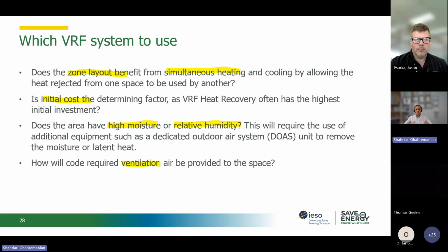Because with the VRF, we don't duct the air through the building, so we cannot add the fresh air to this heating and cooling system, basically. So we need to consider a dedicated outdoor air system, or DOAS system, which most European countries use. So they separate ventilation from the heating and cooling. So that's a good one to have. And basically, DOAS can control both ventilation, or the fresh air that the building occupants need, and also the moisture control, which is the humidification or dehumidification.